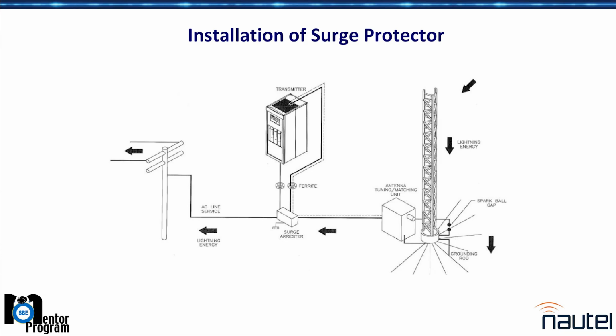If you've got the big lightning rod in the back field, you need a path for all that energy coming down. Think about this: ground has a resistance per foot. If I run 100,000 amps down that tower with 4 ohms per foot, and I'm standing in the field with my feet 2 feet apart, that's 100,000 amps across 8 ohms. Remember, E equals I times R? That's 800,000 volts between the left foot and the right foot, which is why they tell you to put your feet together if you get caught in a field during a storm.